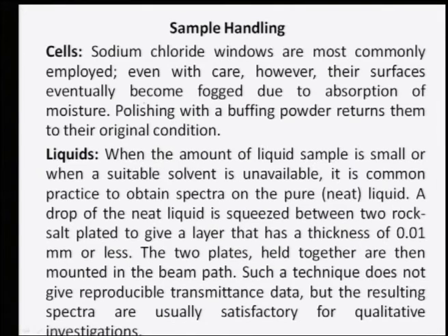A drop of the neat liquid is squeezed between the two rock salt plates, or sodium chloride plates, to give a layer of very small thickness, 0.01 millimeter or less. These two plates are then held together and mounted in the beam path. Such a technique does not give reproducible transmission data, but one can do qualitative analysis with this. That is possible.